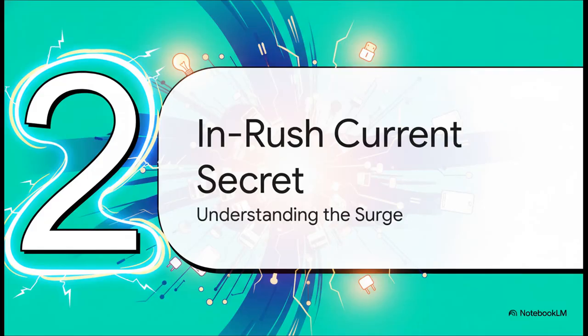So what's causing all this? Why would a breaker trip when it shouldn't, or worse, not trip when it should? Well, it all boils down to this secret little force called inrush current. It's this powerful, hidden surge of electricity that happens every single time you turn something on. Understanding this surge is the absolute key to picking the right breaker.